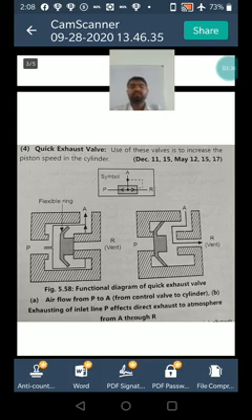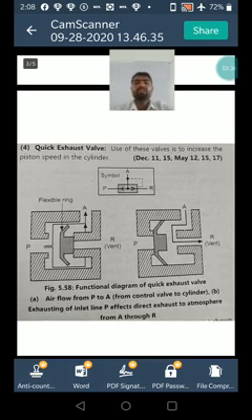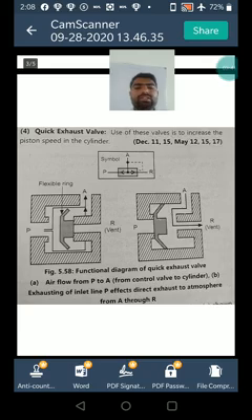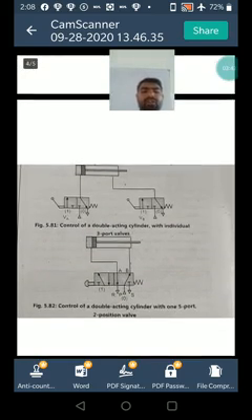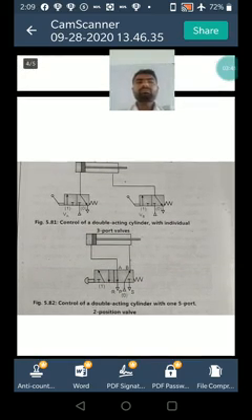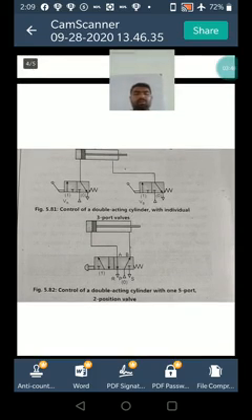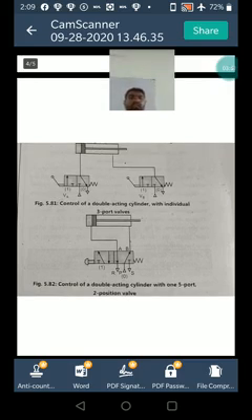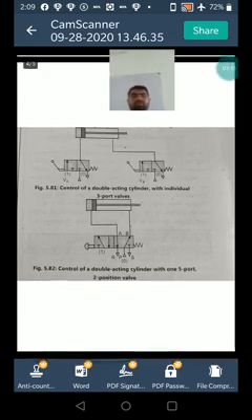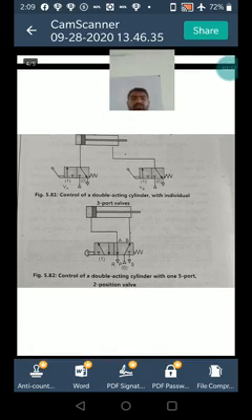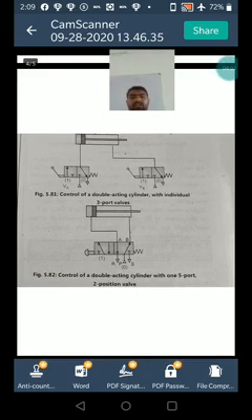This valve is placed directly to the cylinder port. Now we will see the next point, control valve for double acting cylinder. The figure shows extension and retraction position actuated by using two three-by-two valves, whereas the same function is obtained by using one five-by-two valve.